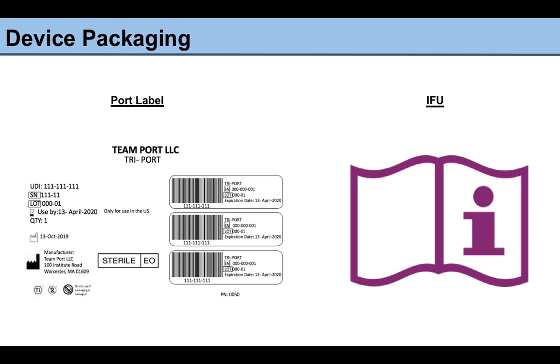Included in our packaging design is the label design for the port. The label design is shown below and indicates various things to consumers, such as the type of sterilization used, which is EO in our case, and that it's a single-use device. The team has also put together an instructions for use booklet, or IFU. This IFU will go over various things such as the product description, indications for use, contraindications, warnings and cautions, possible complications, the implant procedure as well as the injection procedure, any misuses, and the warranty for our product.